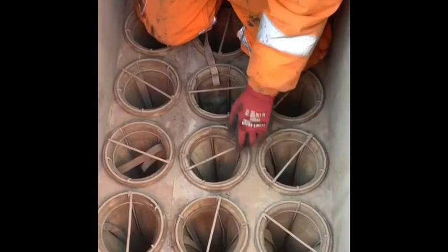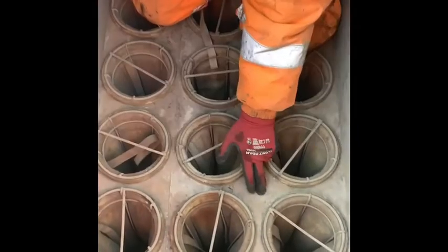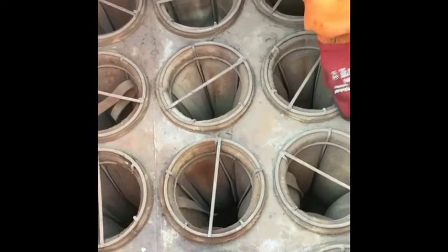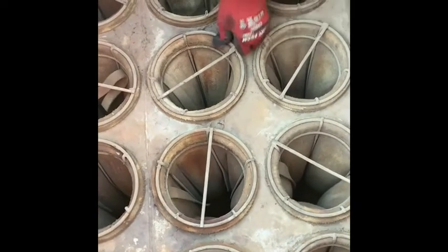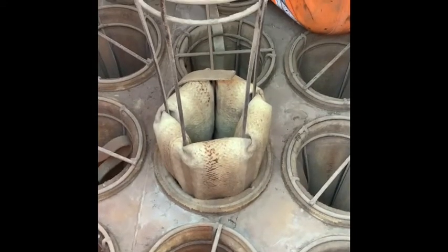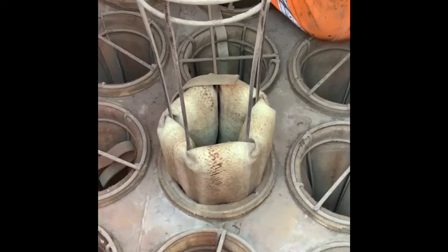I'm inside the cell now and I'm looking for any evidence of filler within the plate. The side walls are nice and clean. I'm looking at the bags, there's no cages that are sticking out, and all the bags are firmly located into position. We're now going to check the bags themselves, and the way to do that is pull the cage up approximately 12 inches and let's have a look at the bags internally.